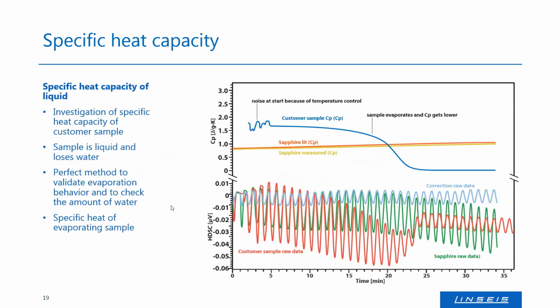Okay, another test was to figure out the amount of water and the CP of the rest of the substances that are inside this solution. The customer asked for a specific heat run for his liquid sample. What we can see here is the light blue curve, which is the correction curve, and the green one is the sapphire calibration curve. And in red, you can see the customer sample raw data.